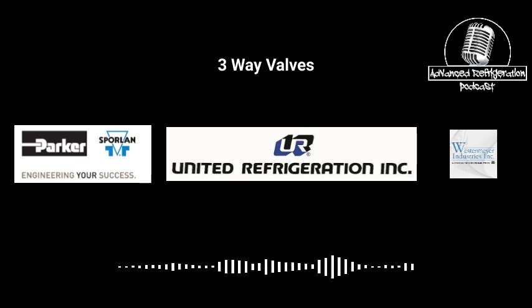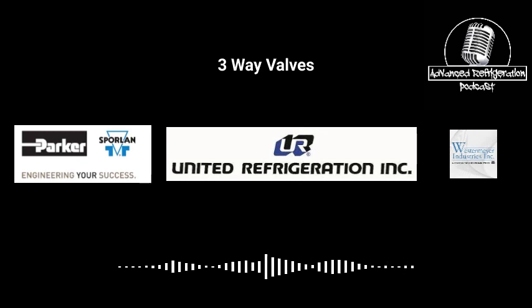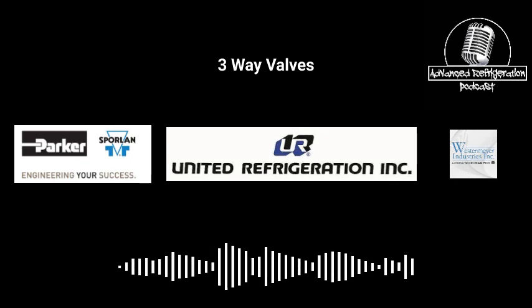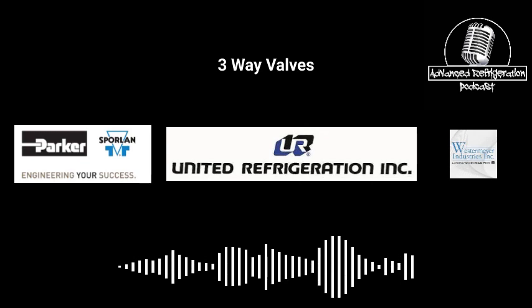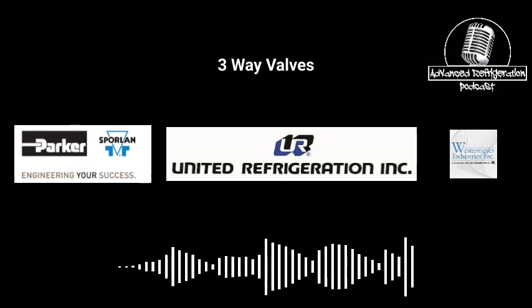Now, these valves, they're fairly simple. I mean, there's not too many pieces to them. You have a pilot assembly, which is going to be directing your hot gas into the chamber and then bleeding off the suction gas. And then you have a plunger assembly. So that plunger is in a tube, and basically that hot gas gets pushed down in the tube, pushes the plunger down, it blocks the hole. And when it shifts the other way, it's going to relieve the pressure and allow the plunger to shift back the other way.